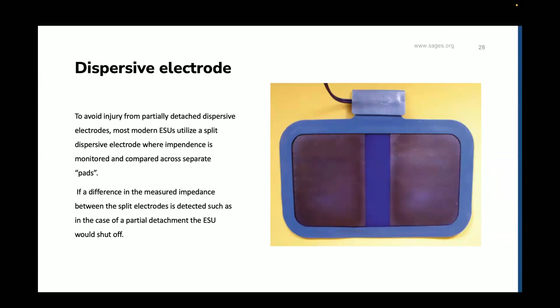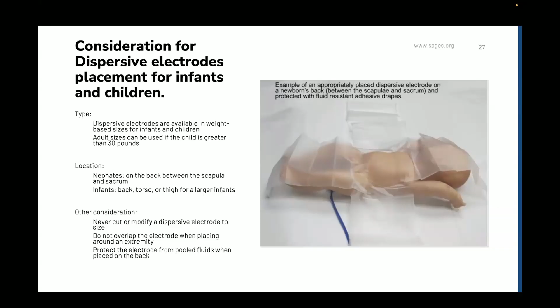Some considerations for when you're placing the dispersive electrode on an infant. You have to use the appropriate dispersive electrode size. There are different weight-based sizes for the electrodes, and generally if the child is above 30 pounds, then you can start to use the adult size. You want to use a larger surface area. In pediatrics, we will generally place them on the back between the scapula and the sacrum. And of course, you never ever cut a dispersive electrode, and you never overlap it. It has to be all in uniform contact with the skin, so you'll never wrap it around a patient's limb such that it overlaps.